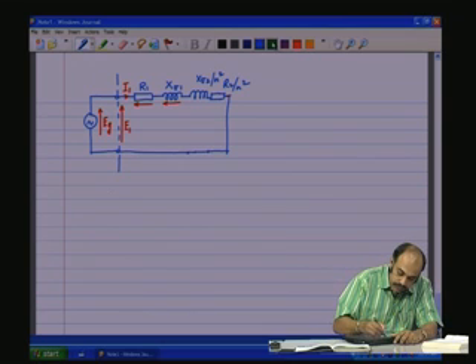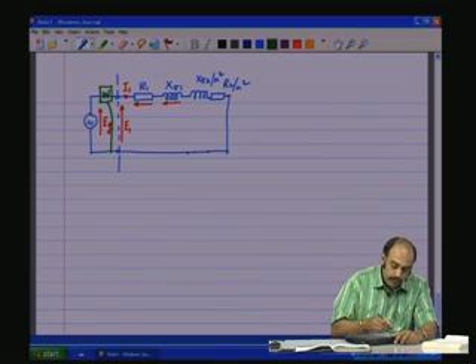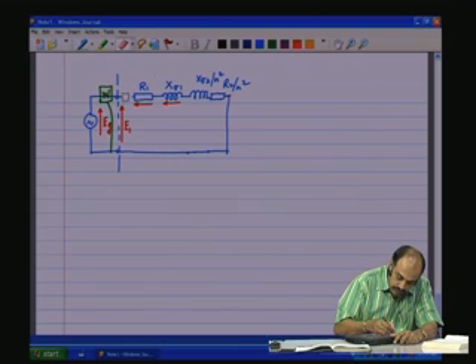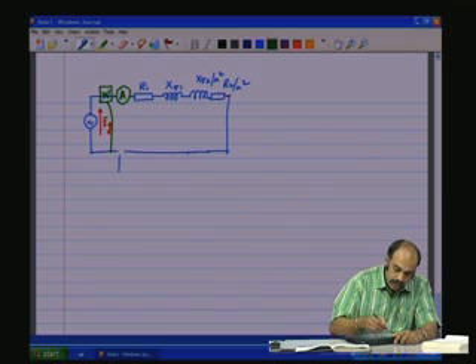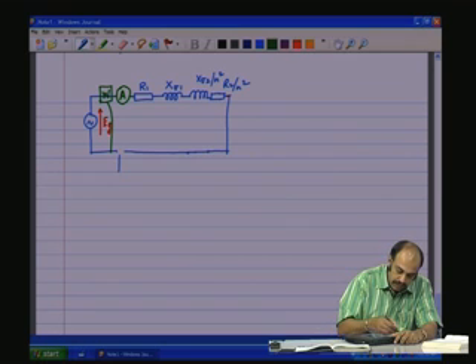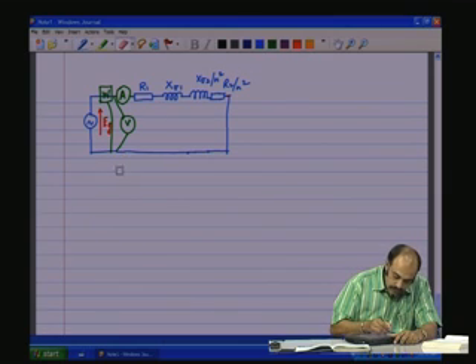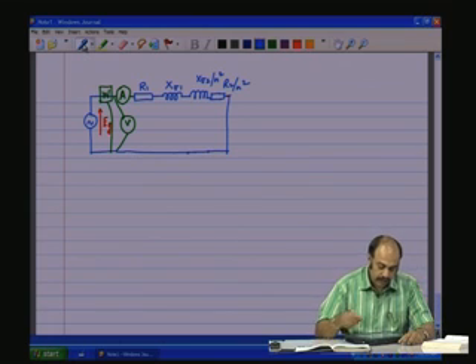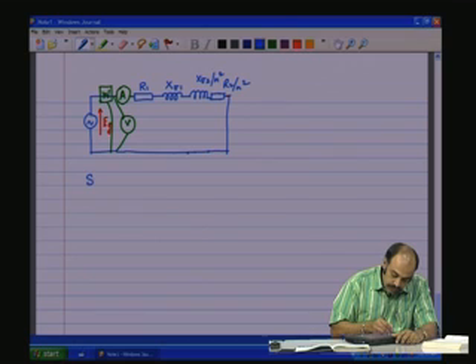So, you continue to keep the wattmeter here. We continue to keep an ammeter here, that is we need an ammeter there, and then we measure the voltage across the primary through a voltmeter. So, these are the changes that happen when you do a short circuiting of the secondary side. So, this is called the short circuit test.